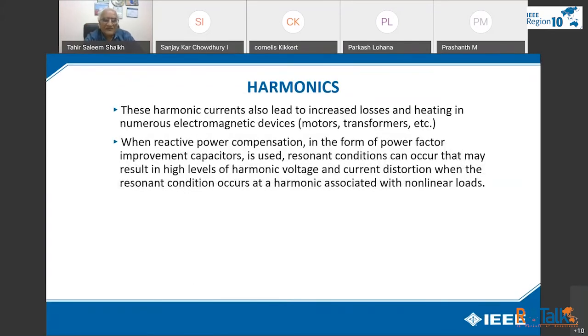These harmonic currents also lead to increased losses and heating in numerous electromagnetic devices, motors and transformers. When reactive power compensation in the form of a power factor improvement capacitor is used, resonant conditions can occur that may result in high levels of harmonic voltage and current distortion, when the resonant condition occurs at a harmonic associated with non-linear loads.